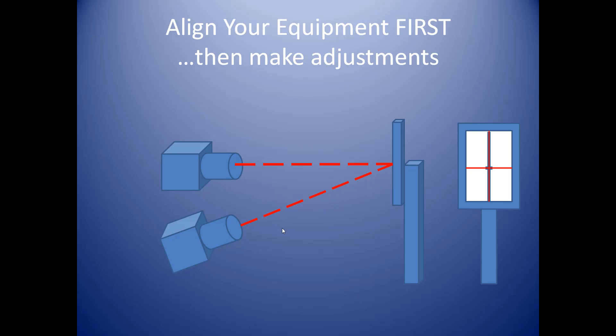You'll want to align your tube centered to the upright bucky with the indicator. Your crosshairs will be centered horizontally and vertically. If you angle the tube, which you will have to do for a couple of these images, you'll want to make sure that once you angle that tube, raise it or lower it, you reorient it back to the center of your upright bucky. You'll also want to load your film into the upright bucky, and make sure that your collimator light is appropriate to the size and orientation of the film.